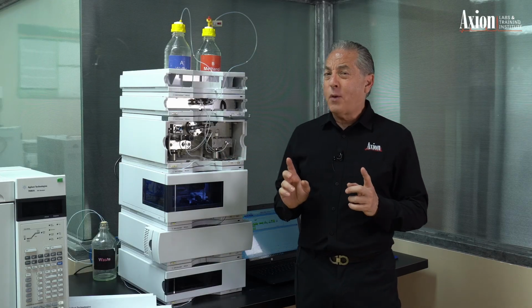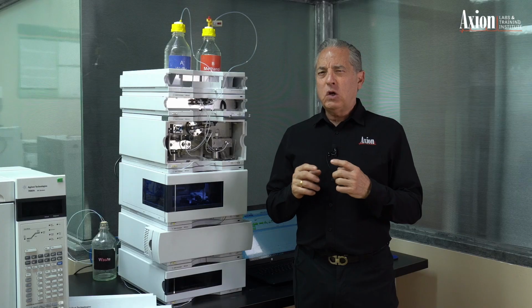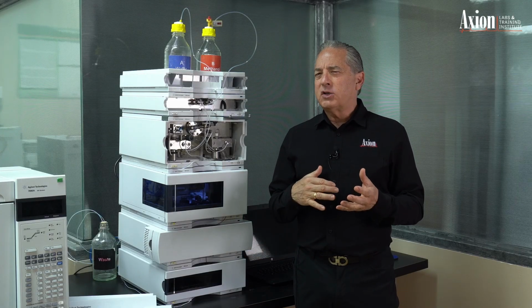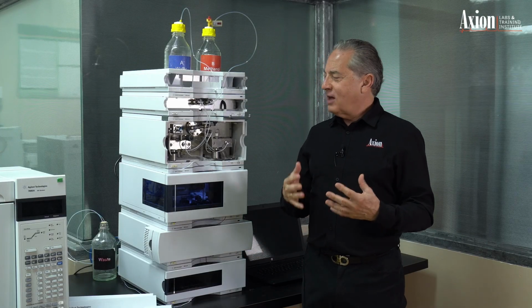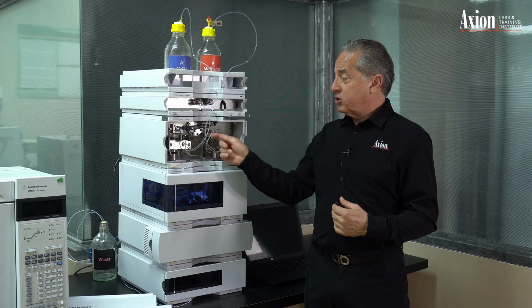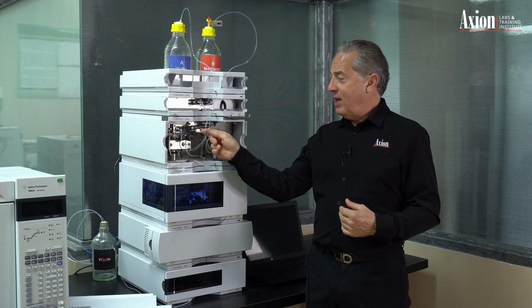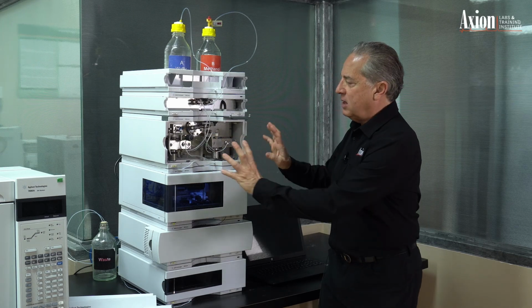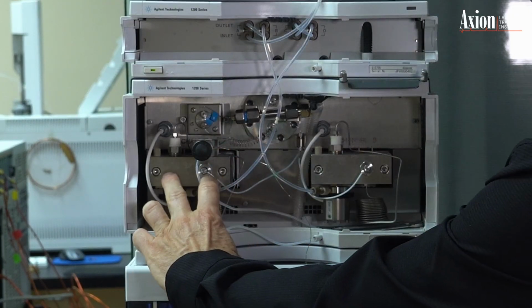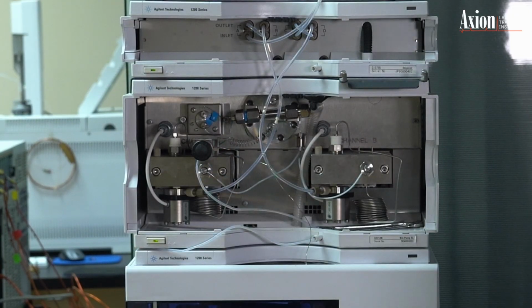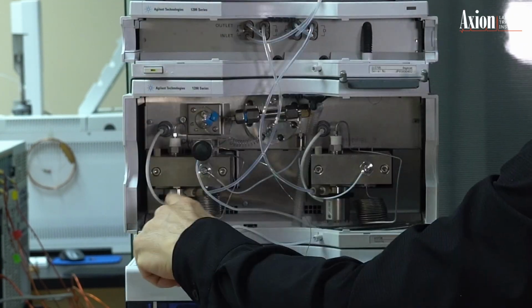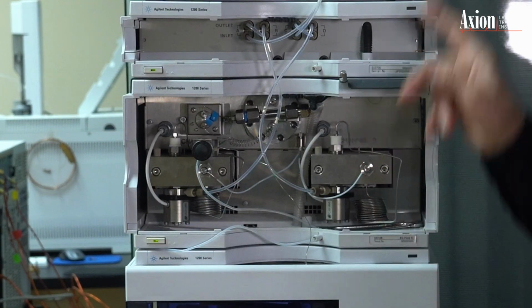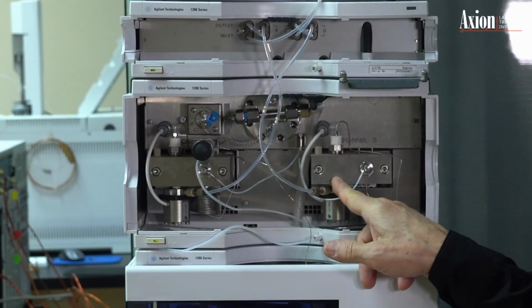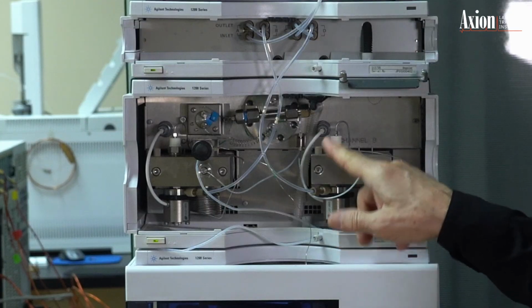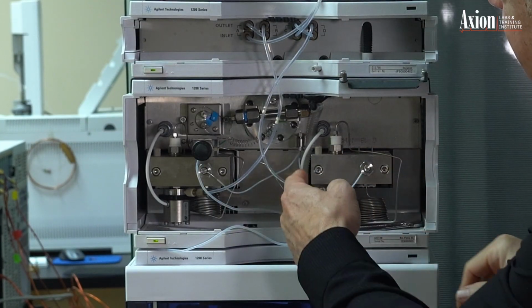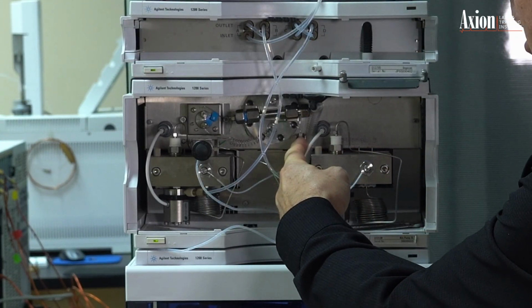It refers to where we blend the mobile phase. Low pressure gradients are still high pressure pumps. It just means a low pressure gradient means we blend on the low pressure side, the plastic tubing side of the pump, and not the high pressure side. In this case, it's called a high pressure gradient because pump A pumps pure water, nothing but water. So pure A comes off of pump A. Pure methanol comes off of pump B. The two are then blended, and I'll take you through the flow path. There's a T right here where the two are blended together.